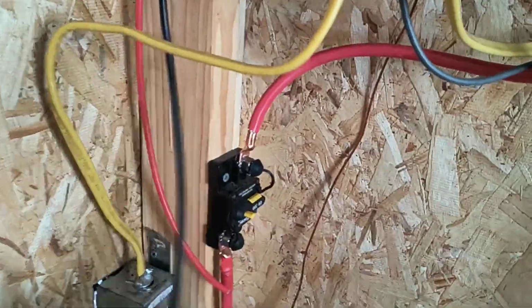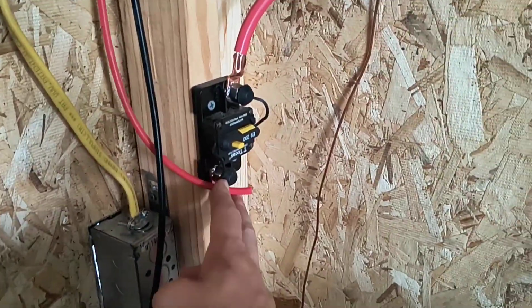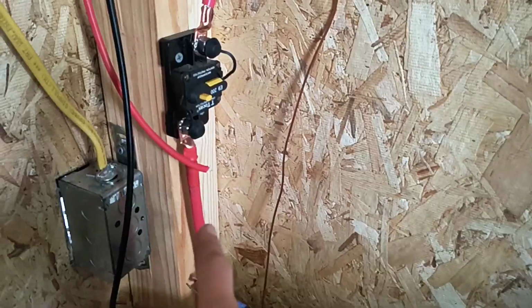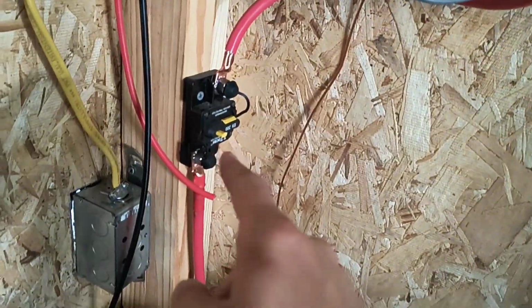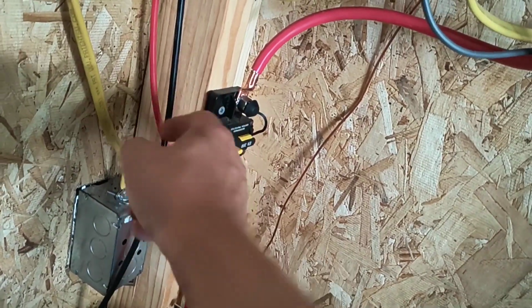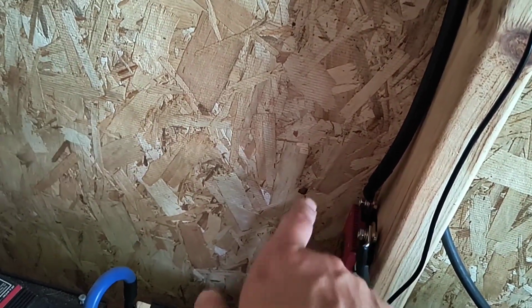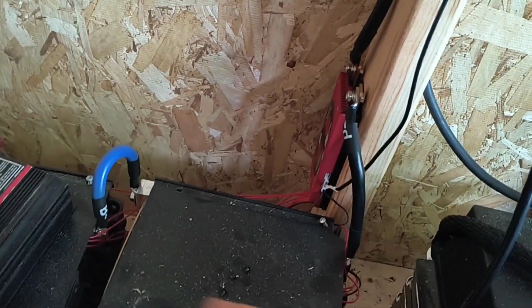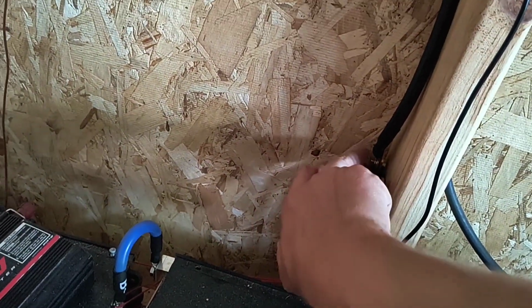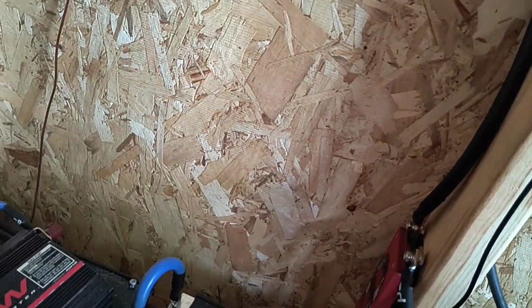I'm going to connect the positive on this side of the breaker going to the battery bank, just so I could shut off the inverter separate from here—I think that would be a good idea. And then the negative one is going to go onto the BMS on the output side, which is also the charge side, so we still utilize the BMS. You don't want to go on this end, because it'll go straight to the battery pack. So we want to go through the BMS, so we're going to go right there.